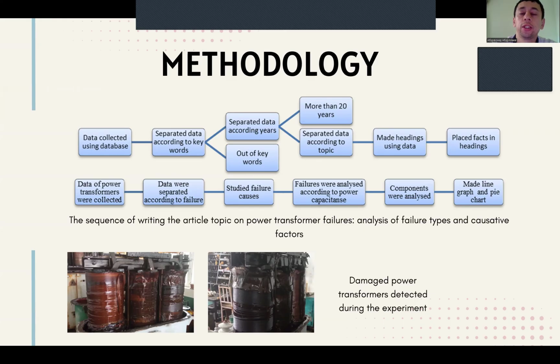After the analysis of the power transformer and its components, and the function of each component, the types of failure and causes of their occurrence were analyzed. The methods of diagnosing power transformers were studied, and the diagnostic methods that were found to have a high level of accuracy for identifying failure in each component were cited. A statistical analysis was conducted on 6-10 kV voltage power transformers in Fergana region. As an aid to research, we used the IEEE standard C57.125. In 2022 and 2023, failed power transformers in the 6-10 kV power grids in Fergana region were analyzed. A line graph displaying the relationship between electricity capacity and the number of failures was constructed.